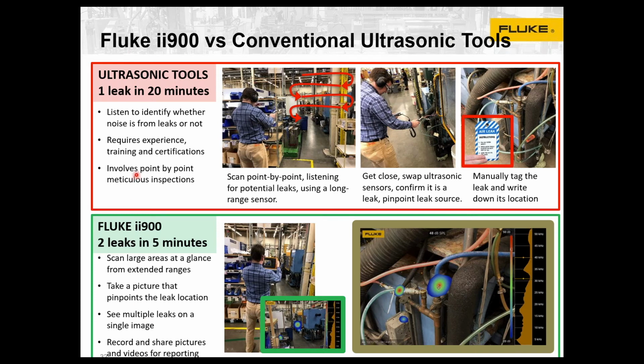This would be an example of a conventional handheld tool. Again, it's ultrasonic. The technology works well. Somebody will be walking around with a handheld tool with either a wand or perhaps a parabolic antenna to pick up ultrasonic noise. The tool then translates that down into audible noise that a trained operator can hear. And I mention a trained operator because they have to interpret: is that sound actually a leak, or is that something else emitting some ultrasonic noise? So you need a trained ear, if you will. It requires experience, expertise, and training on use of the tool and interpretation of what you are hearing. So it's a listening tool, but the user needs to interpret also by listening.